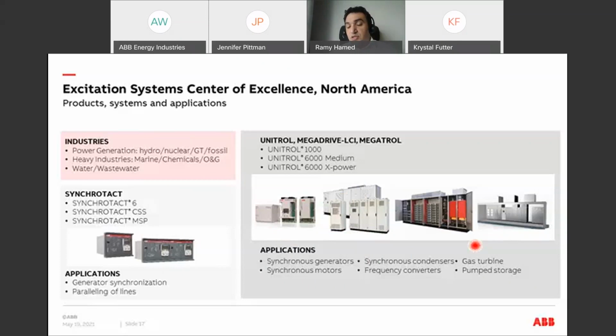And then, as we talked about, we have the LCI, which is a variable speed drive to start the synchronous machine as a motor in different applications, such as the synchronous condenser, gas turbine or pumped storage. And finally, we have the Megatrol, which is a combination of the excitation and the LCI.